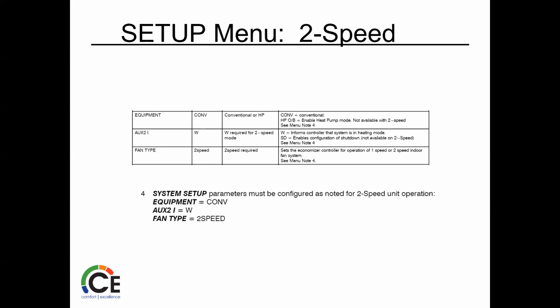The setup menu has 8 configuration parameters and factory default control points. The 3 are critical to staged air volume and 2-speed fan applications. So again, depending on what you're doing, I'm going to scroll down, and you're going to double check that. You're going to make sure that the equipment is in what they call CONV. Your AUX2 I has a W, and your fan type has 2-speed. And again, this is right in your setup, and your instructions are going to have it.